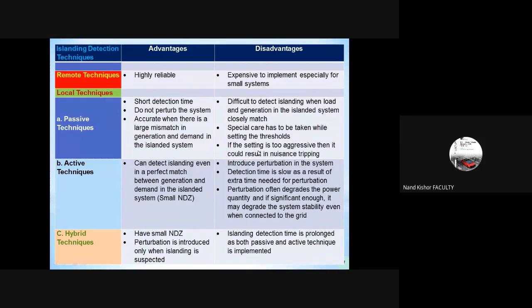And again, if this setting is too aggressive, then it could result in nuisance tripping. By too aggressive, I mean that the system characteristics may be highly dynamic. Let's say in one case you have 3 DGs operating and then line and load and so on. But let's say there is some network configuration change, or maybe the operating condition has changed, then the threshold which we have designed for the islanding decision may result in a bad decision, and thus it may have a consequence resulting in tripping through the circuit breaker. That is one way.